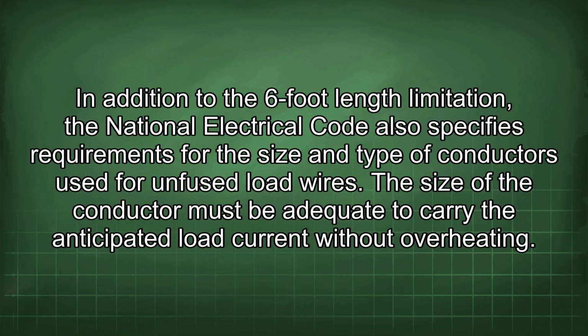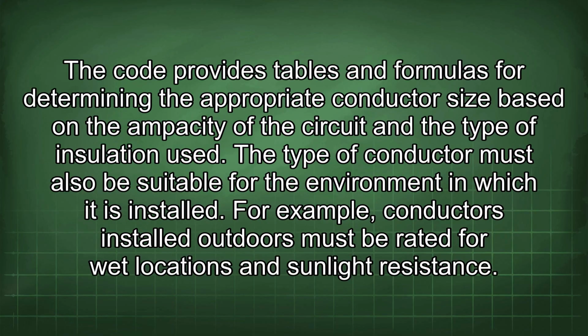In addition to the 6-foot length limitation, the National Electrical Code also specifies requirements for the size and type of conductors used for unfused load wires. The size of the conductor must be adequate to carry the anticipated load current without overheating. The code provides tables and formulas for determining the appropriate conductor size based on the ampacity of the circuit and the type of insulation used. The type of conductor must also be suitable for the environment in which it is installed. For example, conductors installed outdoors must be rated for wet locations and sunlight resistance.